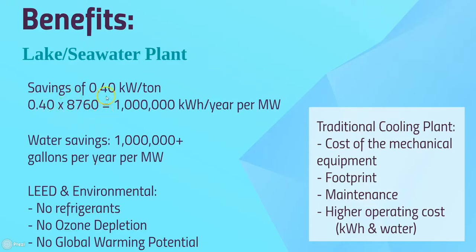Now, you might not be operating a chiller plant at 100% all year long, but the idea is no matter where you're going to be operating it, you're always going to be saving that 0.4 kilowatts per ton over that chiller plant all year long. So you multiply that out, you're getting over 1 million kilowatt hours per year of savings, and that's per megawatt. So if you have less than a megawatt of cooling that you need, say a half a megawatt or wherever you might be at, which is 500,000 kilowatts, you're going to be saving that proportionally about the same.